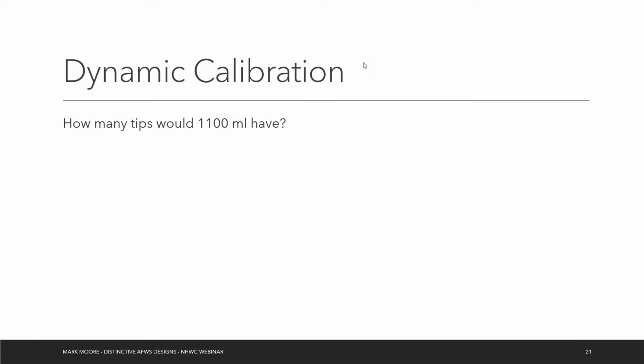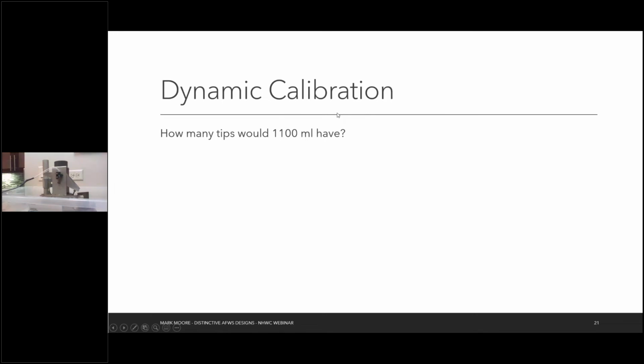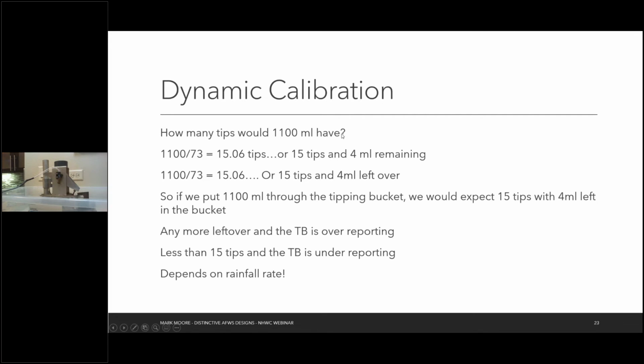So the question is, how many tips would 1,100 milliliters have? Well, we'll take that 1,100 milliliters and divide it by 73. And what we end up with is 15 tips with 4 milliliters left over. So if we put this amount through the tipping bucket and the tipping bucket is working perfectly, we'd expect it to tip 15 times and we'd expect it to have 4 milliliters remaining.